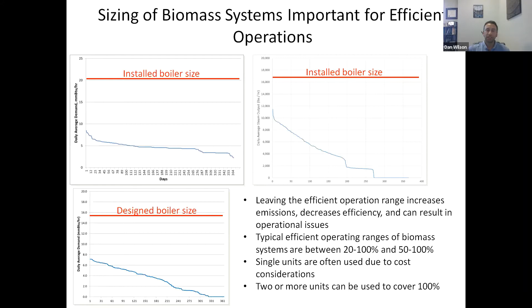The other reason that it's really critical to focus on sizing is upfront cost and economics of the overall system. If you look at the upper left graph, you can see the installed boiler cost or size was maybe 4 times larger than it needed to be if our goal was to capture 90% of the thermal demand of the facility. So what that means is that not only is the boiler bigger, the building is bigger, the storage is bigger, the emission controls are bigger, all the pumps, the piping, everything costs more, and maybe not necessary. It might not be necessary to add that cost into the project if your goal really is to capture that 90% of the load and 90% of the savings. So that's the other reason that's really key to focus on sizing in an efficient way.